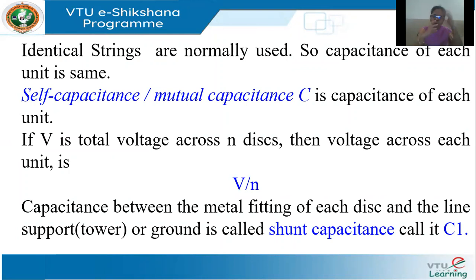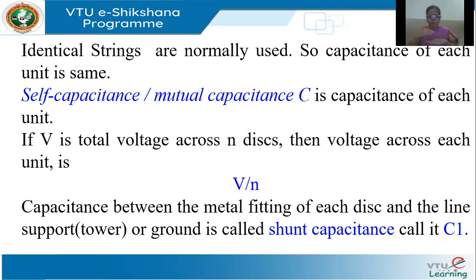Normally, a suspension or string insulator is formed from different disks. How many disks you use will depend on what voltage rating you need. If you use identical disks, the capacitance of each unit will be the same because they're all identical. You can call it the self-capacitance or the mutual capacitance — it's called C. That is for each unit. If I have n disks connected between the conductor and the grounded tower, and V is the voltage, then V by n is the voltage across each disk.